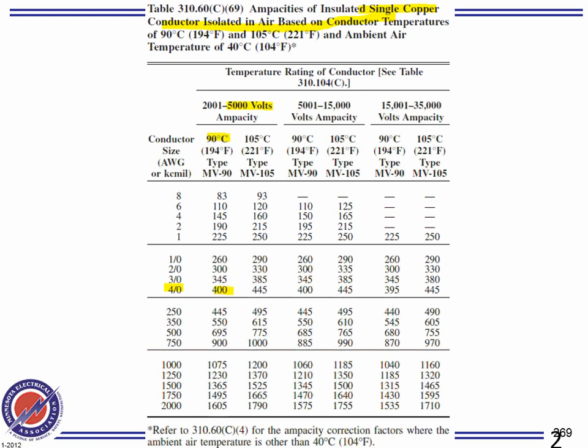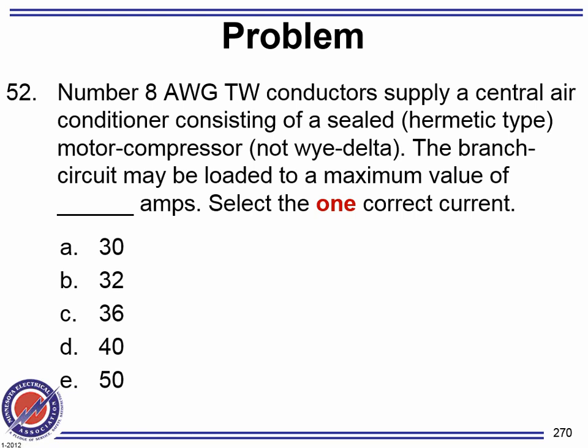So if somebody tells you how much current a conductor like 500 kcm can carry, what would you think? If you put it in conduit, 380. If you put it in a busway, 356. If it's medium voltage cable, it carries close to 495. Any comments, guys, questions about that? Does that make sense? No, yes?